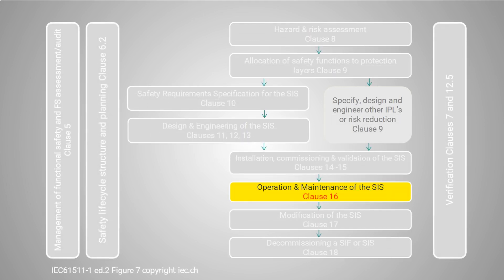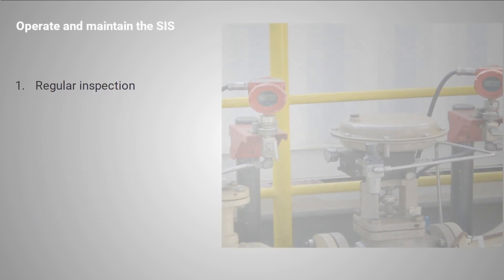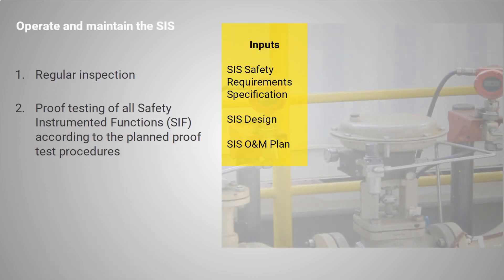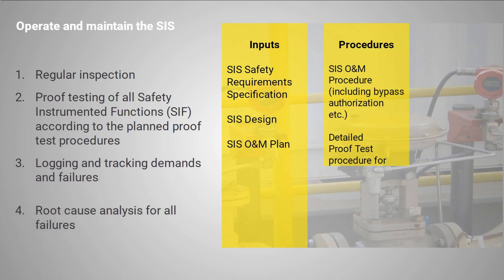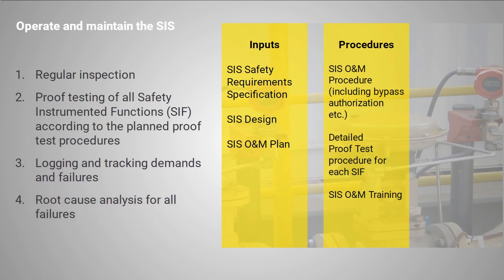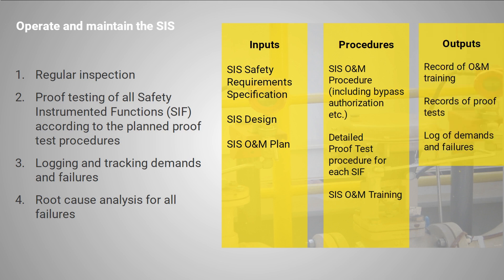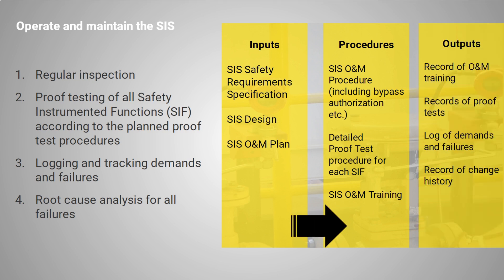Once an SIS is in operation, it is important that equipment is regularly inspected and maintained. Proof test procedures should have been developed for each safety function and these will have a frequency determined by the SIL verification calculation. As demands and failures occur, these should be tracked over time in order to look for negative trends which might lead to plant or system modification.